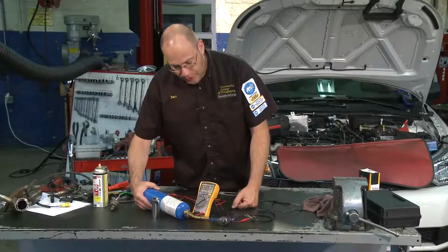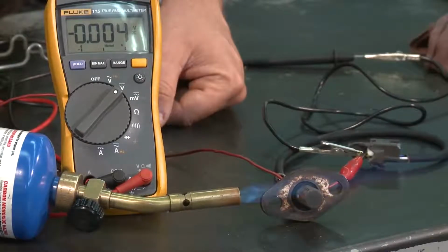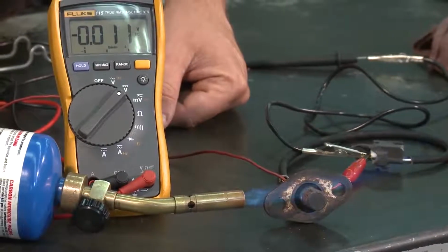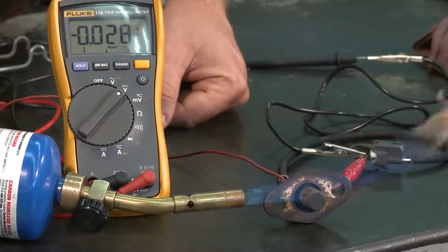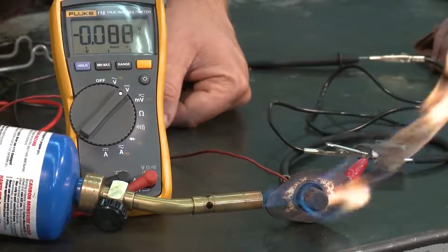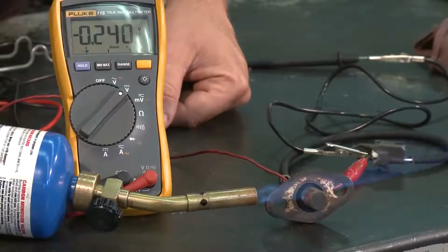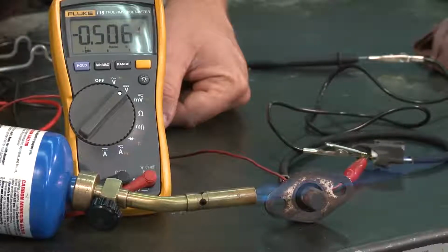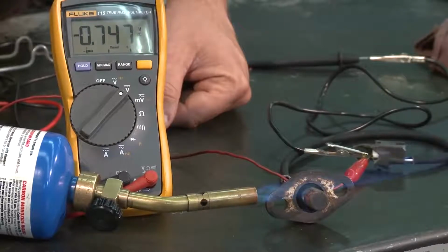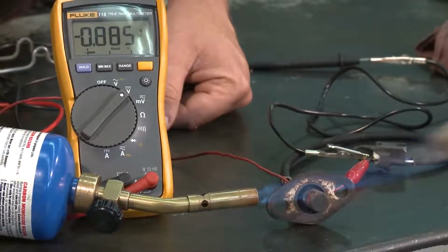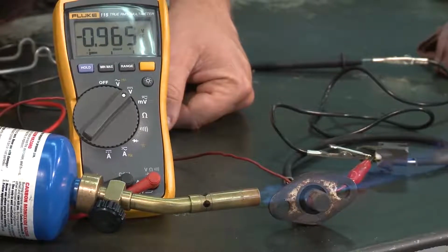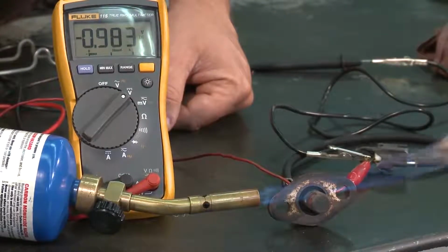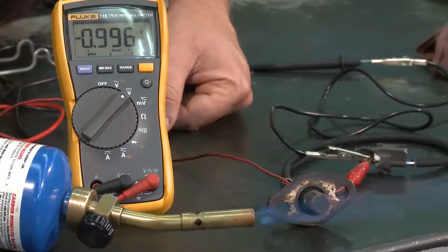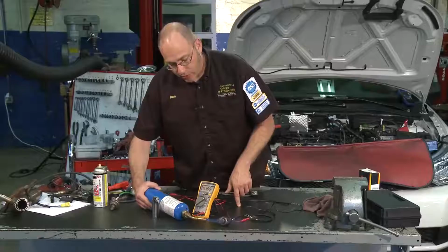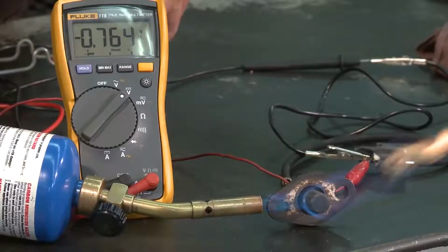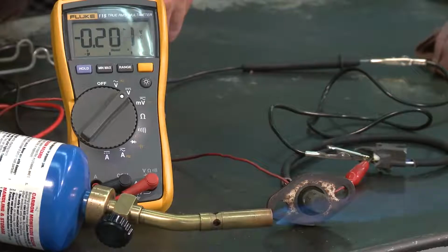We should start to see some voltage come up there. A little bit of voltage coming up as the sensor starts to heat up, and it should almost get to a full volt if everything's working. Right now we're at 40, 50, 60, 70, 80, 90, almost a full volt — not quite, but pretty close. As soon as I pull the flame away, it should immediately drop. If it goes hot, it should heat right back up to where it was, and if I pull it away, it should drop quickly.